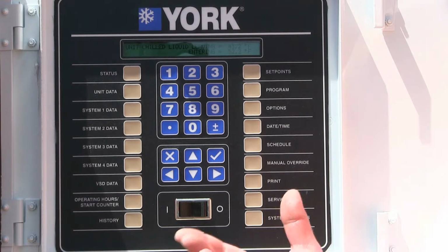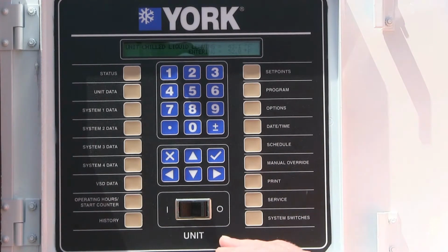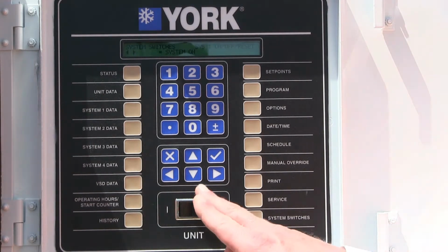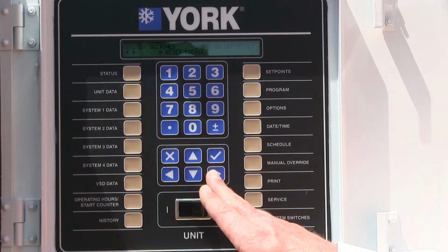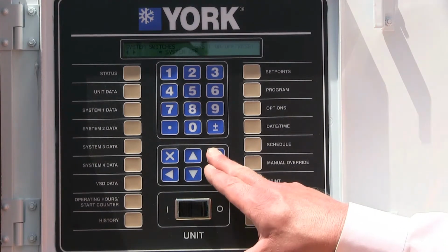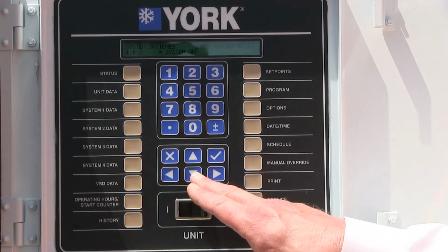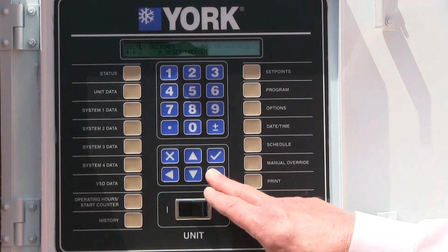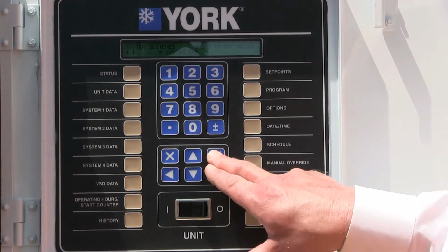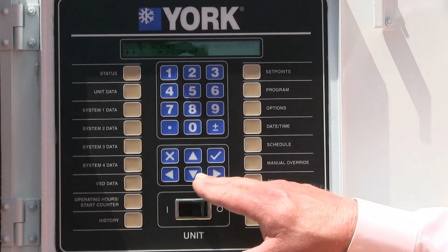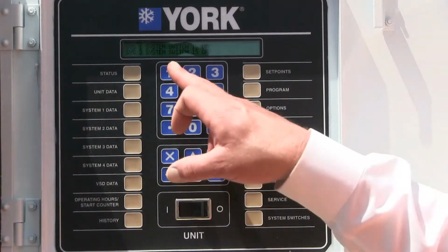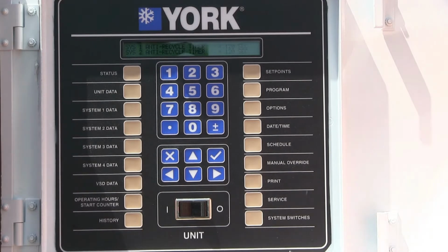But just to recap, I'm going to go ahead and shut the machine down. And by doing that, I'm not going to turn the switch off. I'm going to go into system switches, and I'm going to turn system 1 to off. Right there, I'm going to push the check mark. And then I'm going to go down to system 2 and turn that one to off and push the check mark. And that's going to lock our machine out. I go back to status, it's going to say system switch is off. And that's the proper way. Now that's the rotors back spinning on the screw compressor. That's the proper way to shut the machine down.